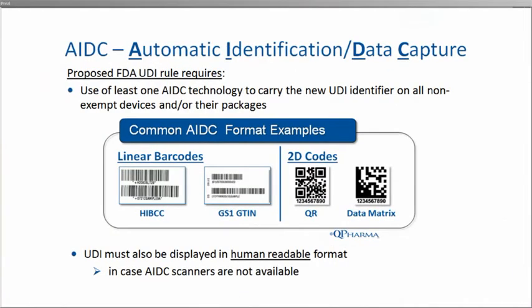AIDC is the carrier or label that displays or transmits the UDI data to scanning or radio technology. Common AIDC formats in use today are linear or 1D barcodes, like the HIBCC and GS1 codes on the left, and 2D codes like QR and data matrix on the right. Radio Frequency Identification, or RFID tags, are also expected to be an acceptable format for Automatic Data Capture. But since the final rule is expected to call for labels that are human-readable, if you use RFID, there still will have to be a human-readable label in case scanning or RFID reading tools are unavailable.